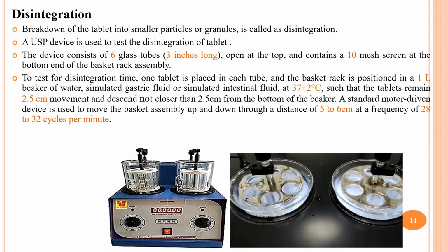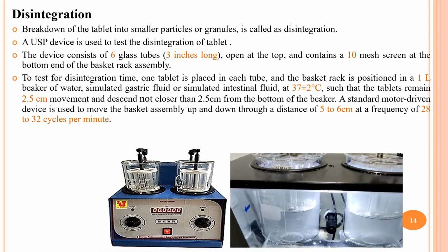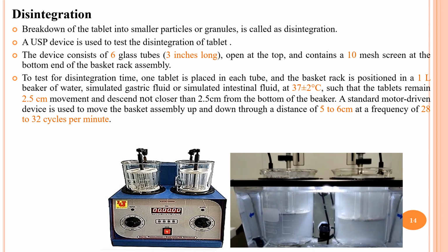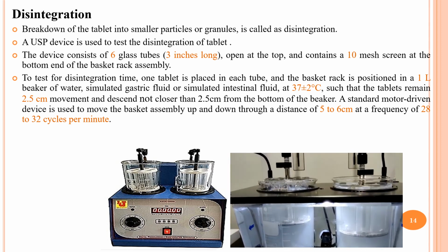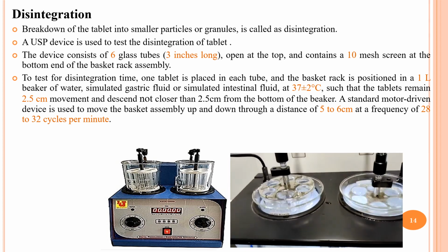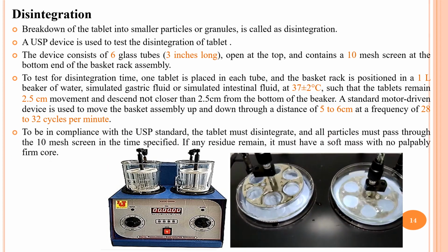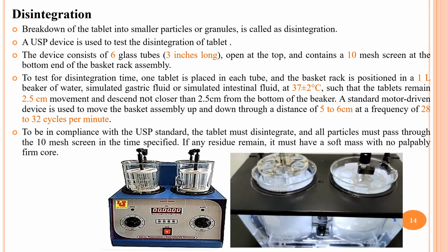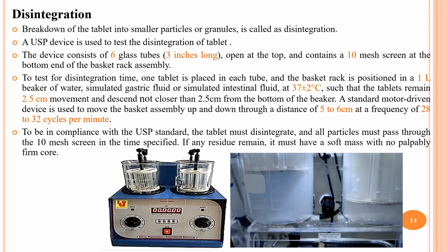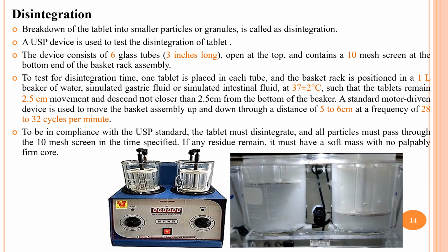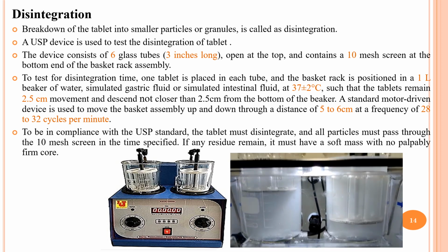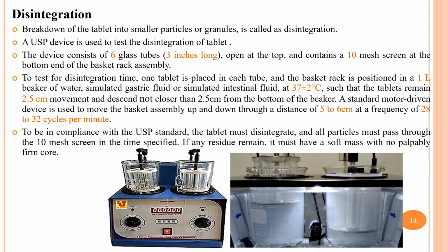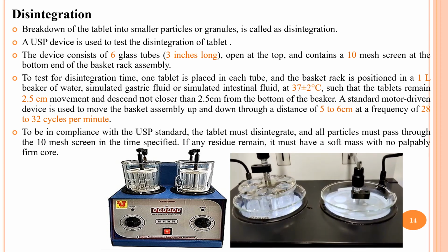A standard motor driven device is used to move the basket assembly up and down through a distance of 5 to 6 centimeter at a frequency of 28 to 32 cycles per minute. To be in compliance with USP standard, the tablet must disintegrate and all the particles must pass through the 10 mesh screen in a time specified. If any residue remains, it must have a soft mass with no palpably firm core.